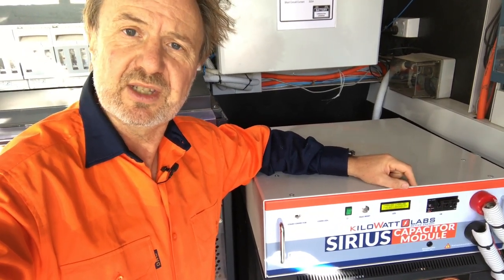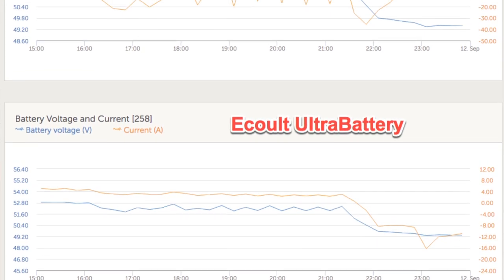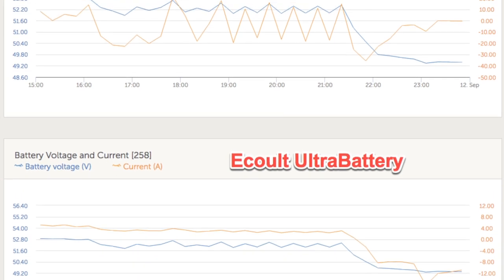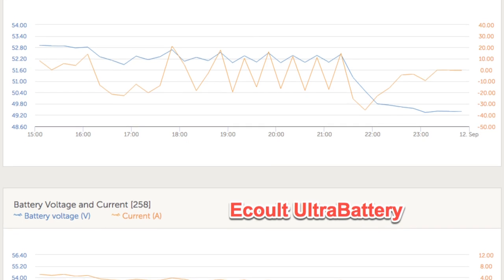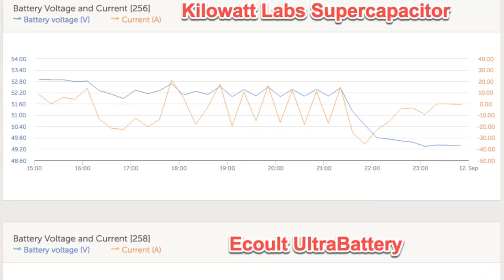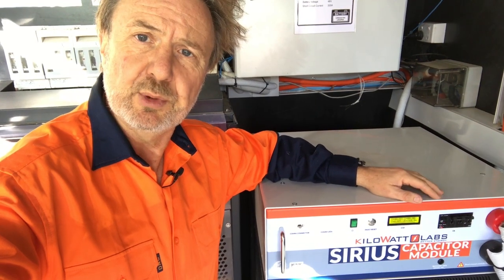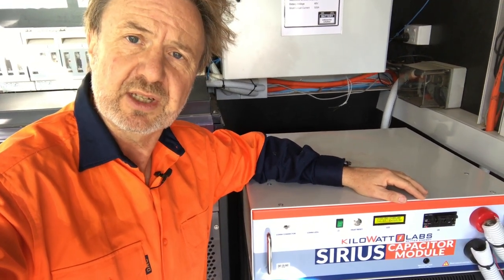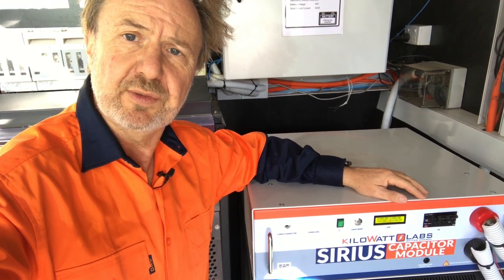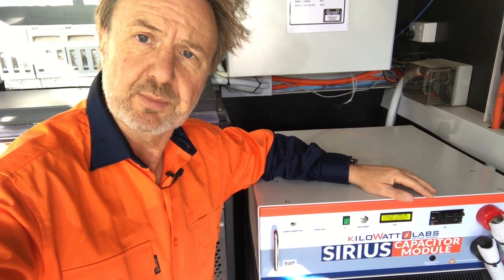During the charge and discharge cycles, it jumps in first, basically — charges first and then discharges first. When we look at the logs for the two batteries, we notice that something like six or seven times a day or more, the supercapacitor is cycling. So we're getting a lot of cycles out of this rather small pack, which is supporting a larger battery system — the UltraBattery with about 16 kilowatt-hours of usable capacity — as the main energy store for the microgrid.